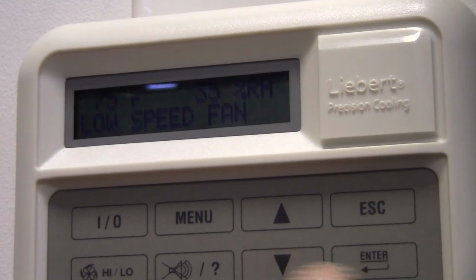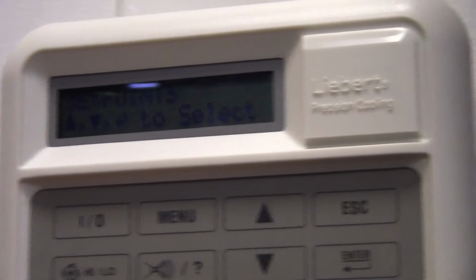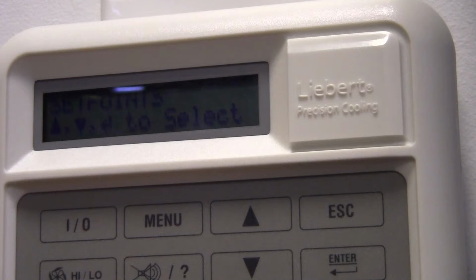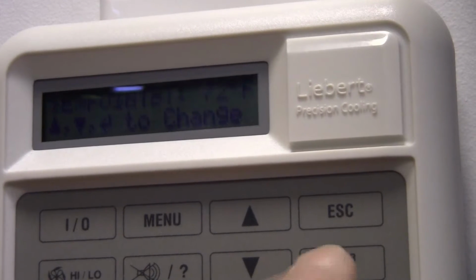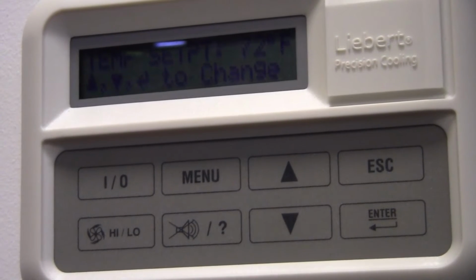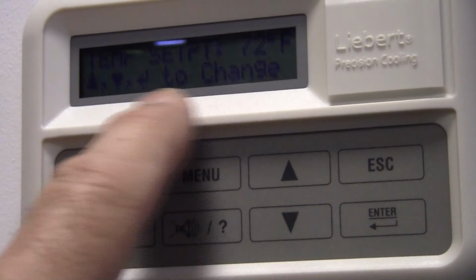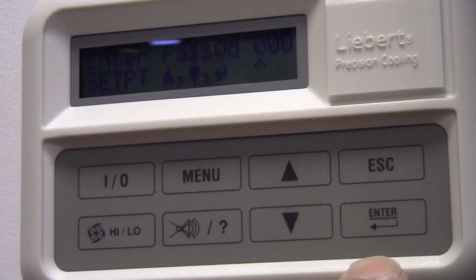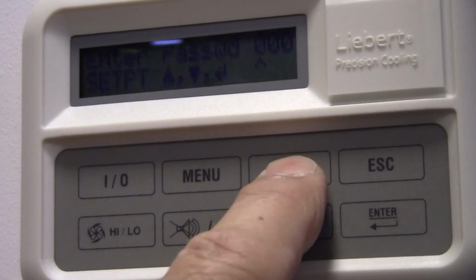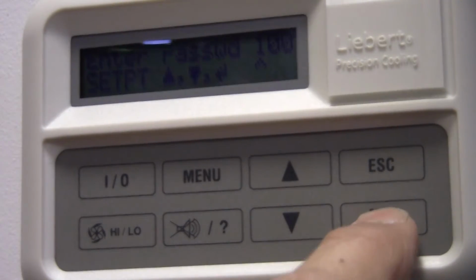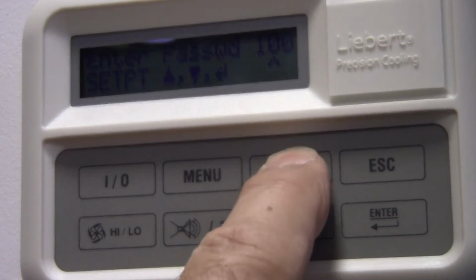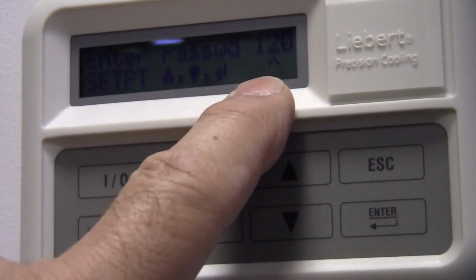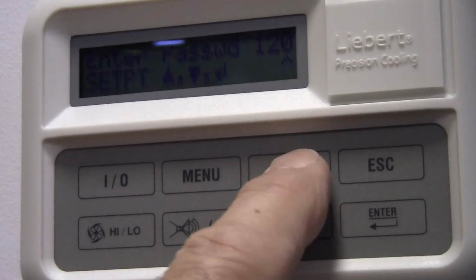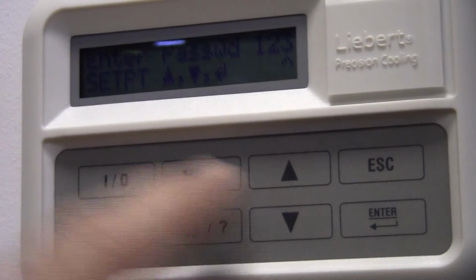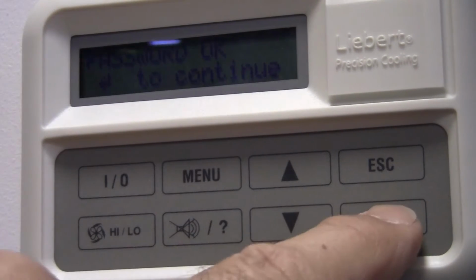So the way you do that is you hit the menu button. Then what you're going to do is you're going to hit set points, enter. Try to get this so you can see everything. Then you hit the enter button to change. I want to change it. It's asking for your password. You hit the up button. The number 1 populates up there, and then you hit enter. It goes over 1 digit. Go and hit the up button till number 2 populates. Hit enter. The 3rd digit, 3, enter. The password is okay, enter to continue.